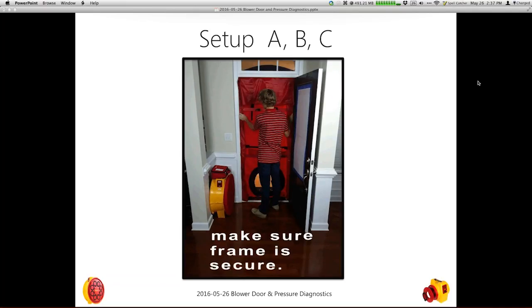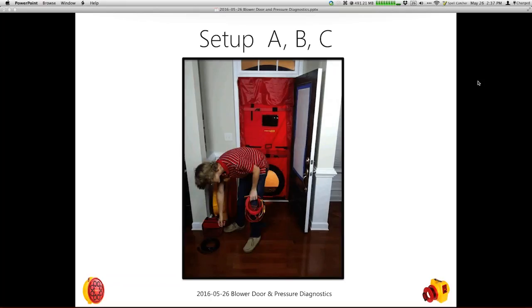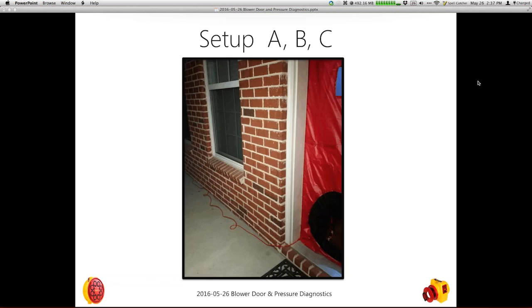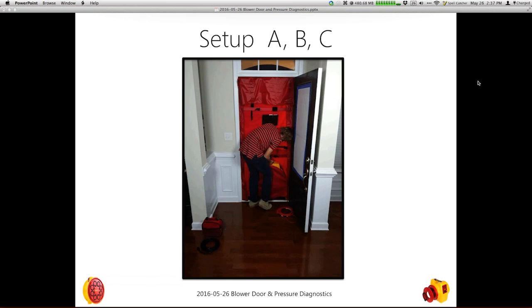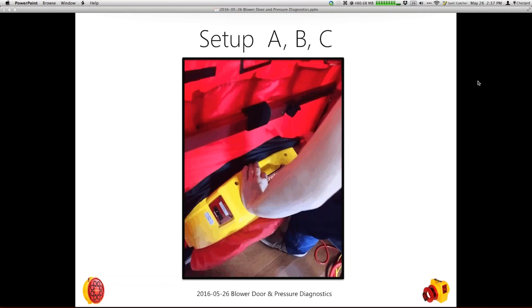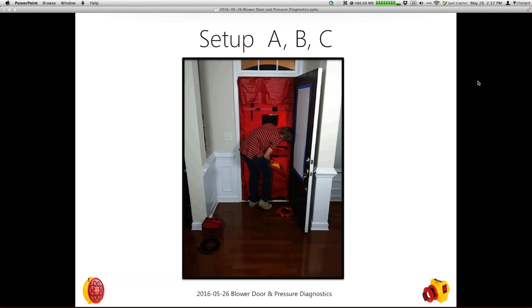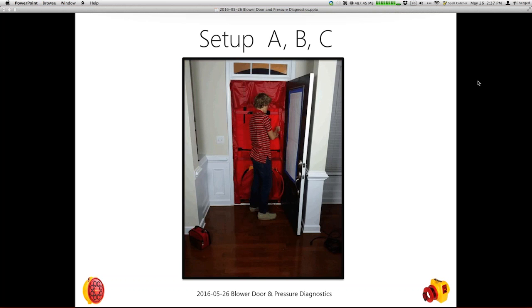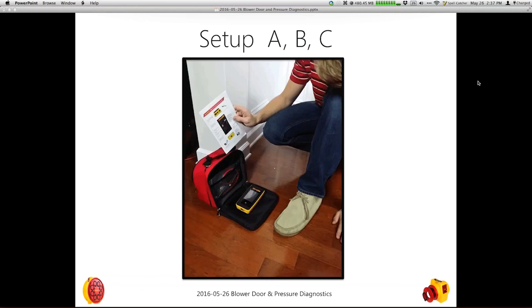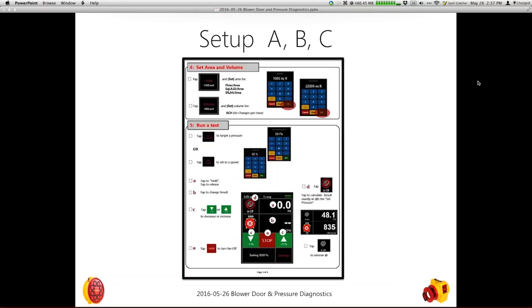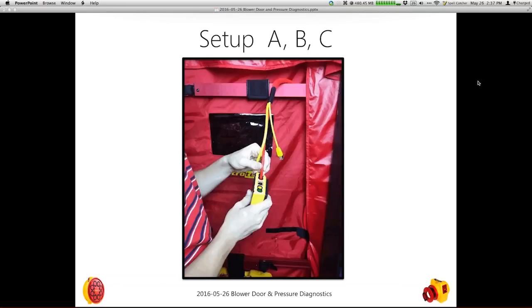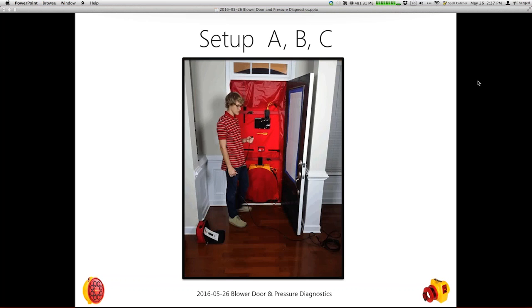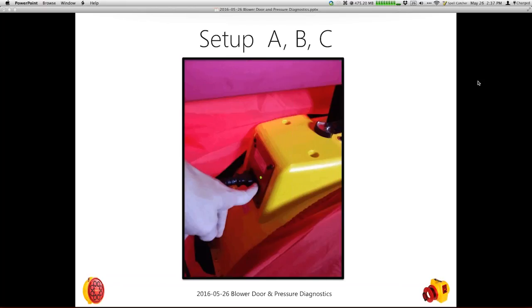And now I'm going to set up the DM32, which initially when you turn it on, it will actually go to the exact same place where you left it off. It's an amazing, simple feature, but it's very helpful. You can tap baseline, it'll acquire the baseline, and then you can set the baseline. The new system, this is the older 1000, the new one actually has only an A, B, and fillers that go along with that. So we recommend people do a set to 25, check to make sure no loud booms, nothing happened, and then you get your results as you need them at 50 pascals.